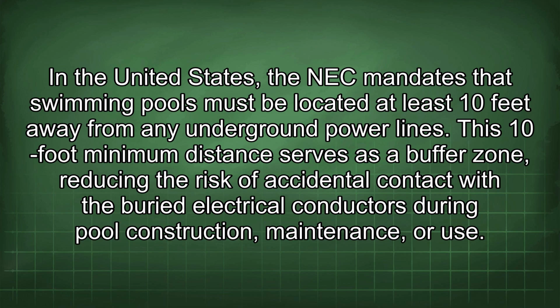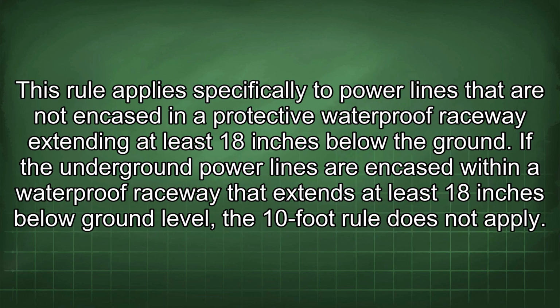any underground power lines. This 10-foot minimum distance serves as a buffer zone, reducing the risk of accidental contact with the buried electrical conductors during pool construction, maintenance, or use. This rule applies specifically to power lines that are not encased in a protective, waterproof raceway extending at least 18 inches below the ground. If the underground power lines are encased within a waterproof raceway that extends at least 18 inches below ground level, the 10-foot rule does not apply.